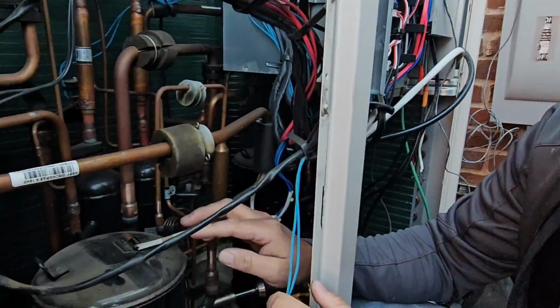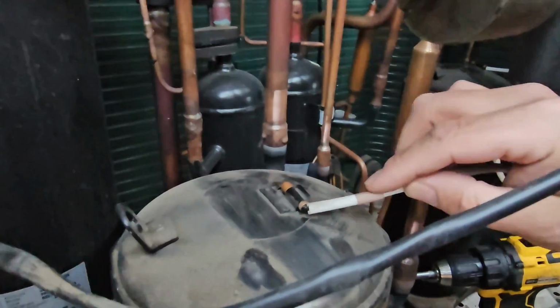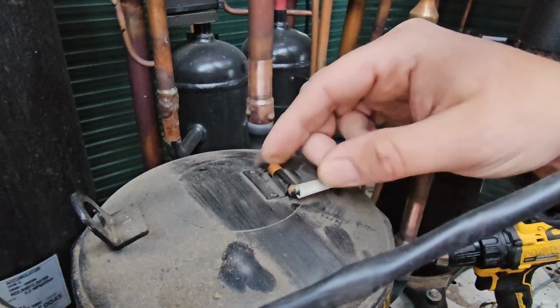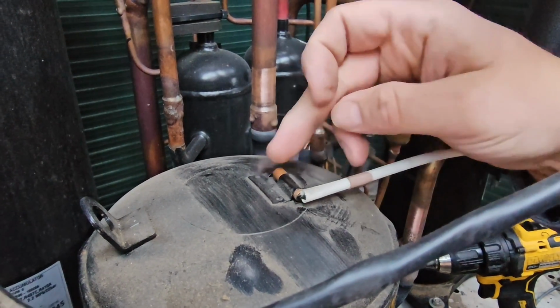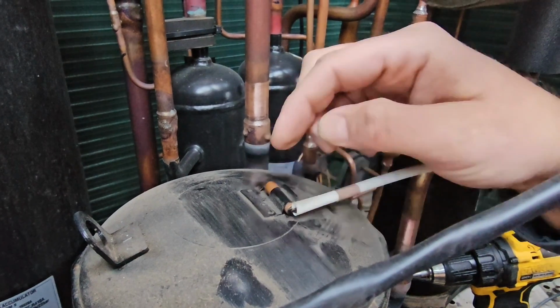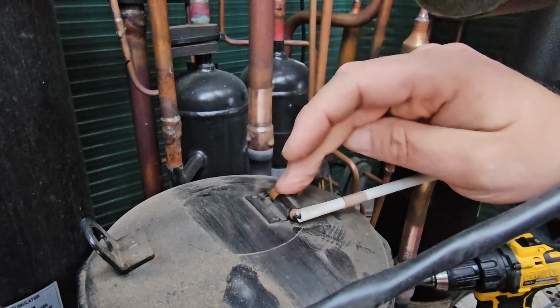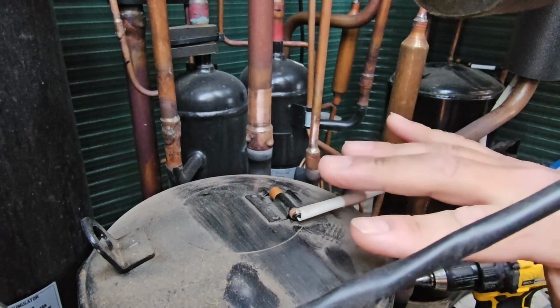Now that we've recovered all of the refrigerant, we can start the process of removing the pipe connections from the old compressor. So I want to show you how to identify each pipe. First, I'm going to show you this thermistor that's on top of each compressor. This is the top thermistor, and this is an overload protection, basically. So we're going to remove this before we can remove the compressor.